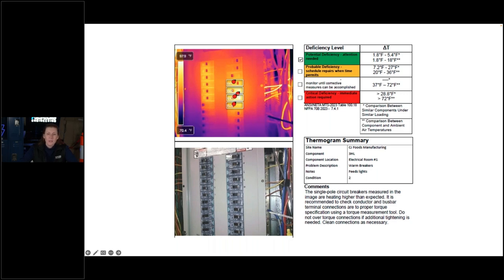In this example there are single pole breakers with higher heating than expected for the environment and anticipated load. A lot of times this comes from loose connections. We know the load isn't overdrawing, but maybe something's loosened up or needs exercising, so we've given comments and examples depending on the situation for how to correct this.